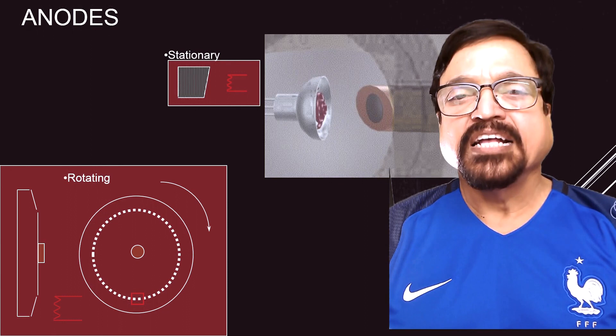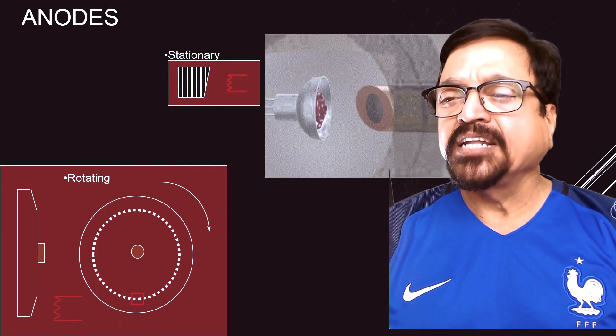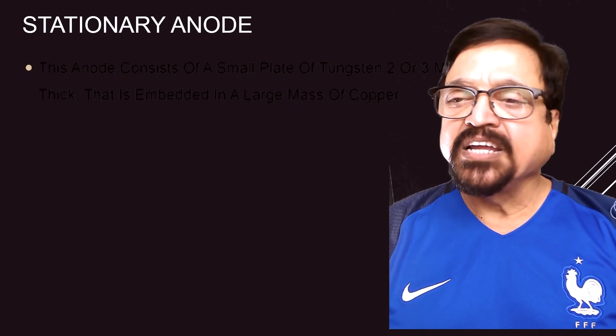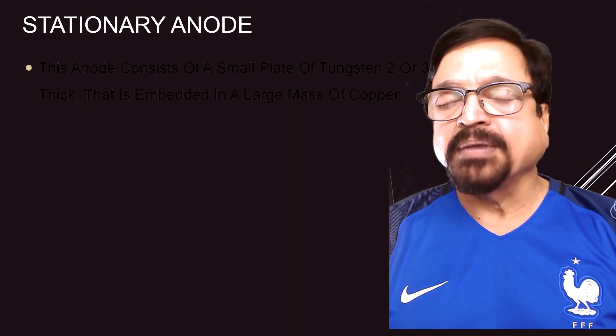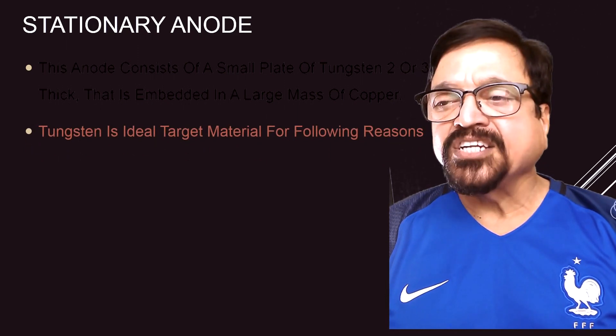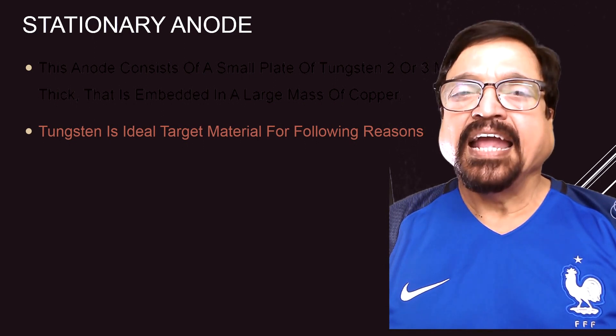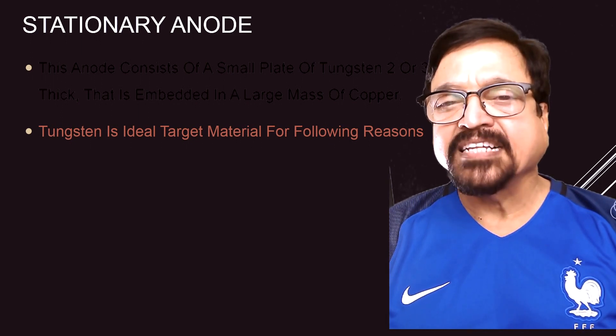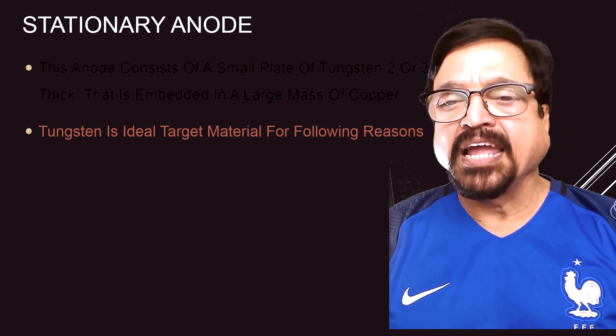Now we are going to see the stationary anode. This shows a stationary anode — it doesn't move. Outside it is copper and the focal spot is of tungsten. The material is the same as the rotating anode but the design is different. This anode consists of a small plate of tungsten, 2 to 3 millimeters thick, embedded in a large mass of copper. Copper is a very good conductor and tungsten has a very high melting point — that is why the combination is used. One material accommodates the huge heat production and the other dissipates it.